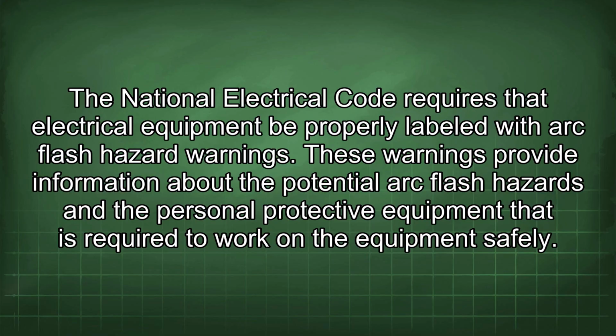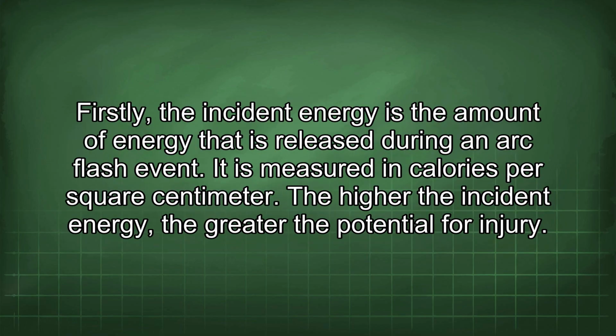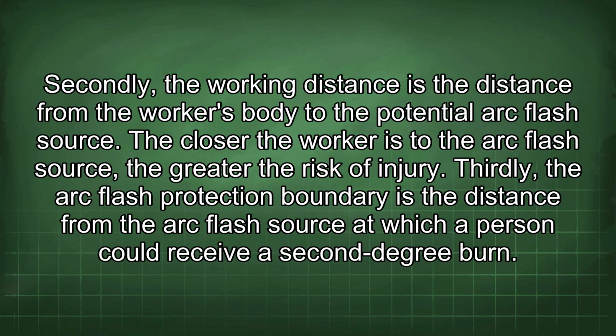Firstly, the incident energy is the amount of energy that is released during an arc flash event. It is measured in calories per square centimeter. The higher the incident energy, the greater the potential for injury. Secondly, the working distance is the distance from the worker's body to the potential arc flash source. The closer the worker is to the arc flash source, the greater the risk of injury.